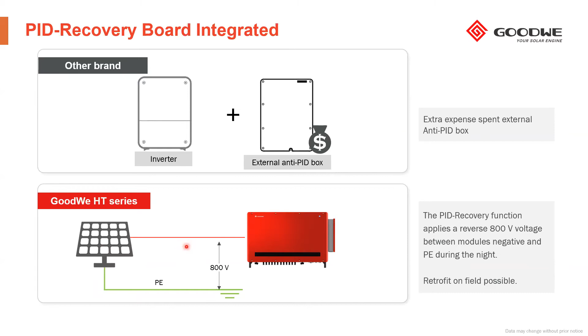So if you're designing a PV plant and you're not sure about the quality of the modules, and you know the location has a very high humidity level, you should consider, at least from a design point of view, adding the PID solution.